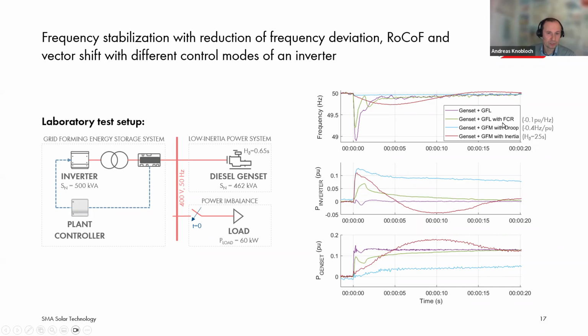If we operate our inverter also in grid following mode, but with some frequency containment reserve, so primary control, which has some delay, and the delay in the response was almost 2 seconds, we see that our inverter provides some response. It measures the frequency, and based on this frequency and the adjusted droop slope, it provides some power, but with some delay. So instantaneously our diesel generator again absorbs most of the power. But since the inverter also starts to react at some point, the deviation is not that high. The frequency gradient is still the same as the initial one, but our frequency nadir is not as low compared to the case where we have no frequency containment reserves available.